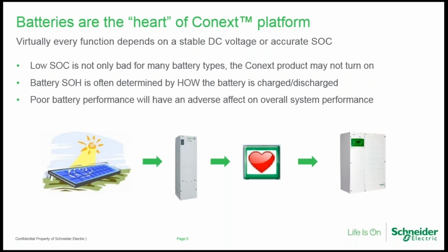Low state of charge is not going to be healthy for flooded battery types. State of health is often determined by how the battery is treated. So if you have a state of charge tolerant battery chemistry, then it's going to be more tolerant of partial state of charge, and you're not going to have to worry about discharging it too deeply or leaving it at a particular low state of charge for extended periods of time. Poor battery performance is going to be evident by poor system performance.